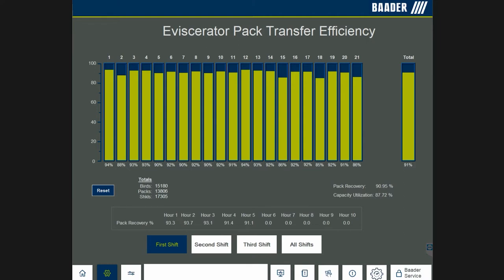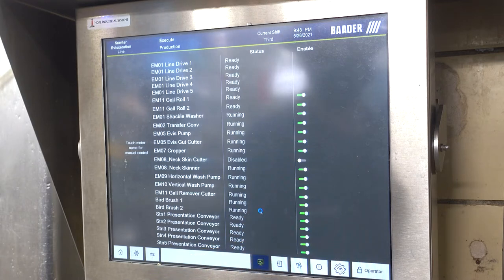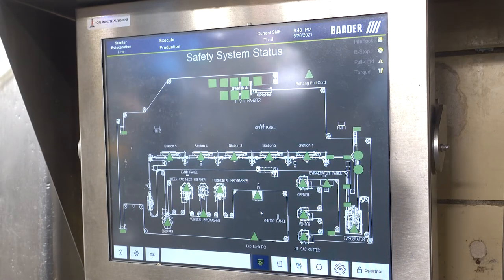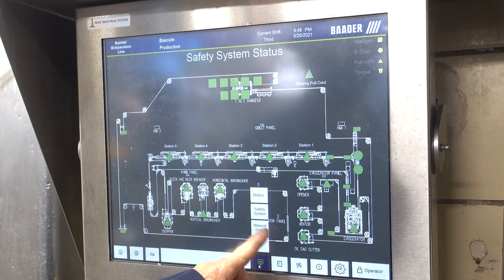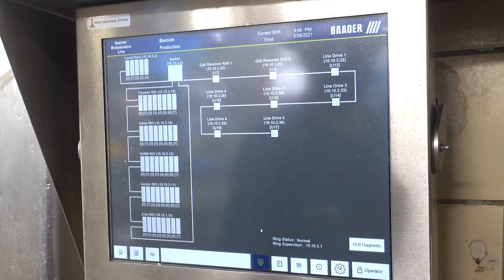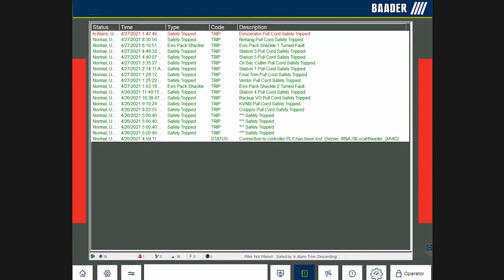Capacity utilization is also displayed to represent how many birds were on available shackles, showing missed opportunities. Traditionally, plants have no ability to recognize where a safety fault has caused the line to stop. These safety faults can come from a variety of sources, such as e-stops, pull cords, torque overload, and interlocks. The Baader system identifies where the safety fault occurred, then automatically presents and logs the cause.